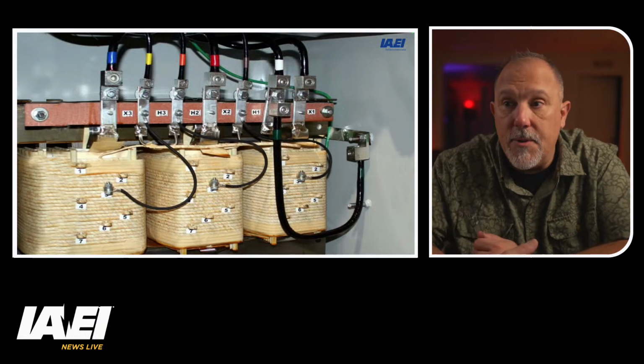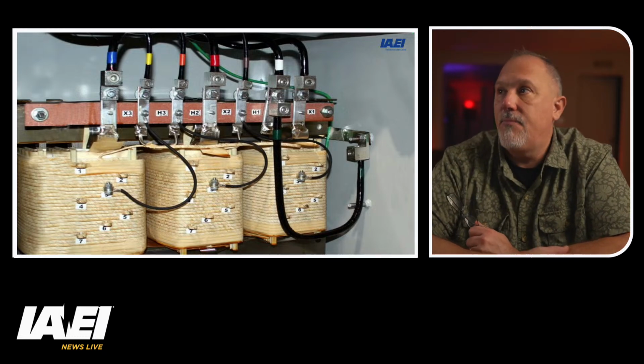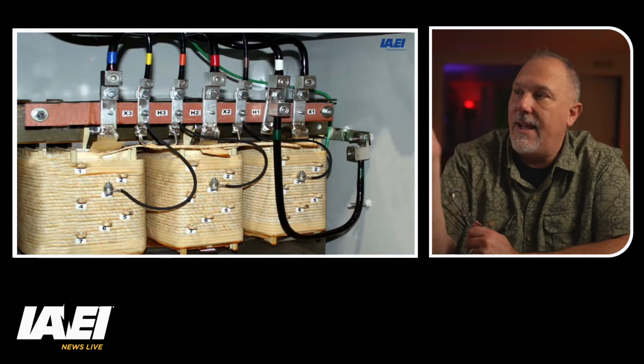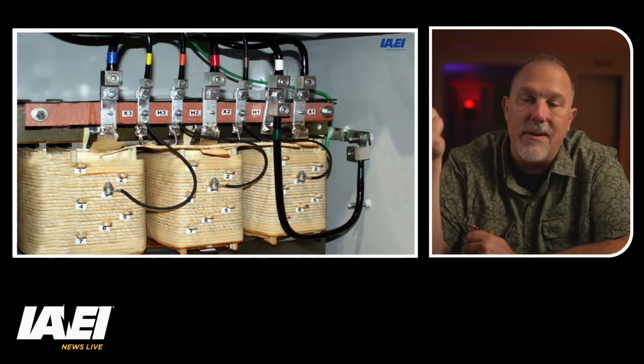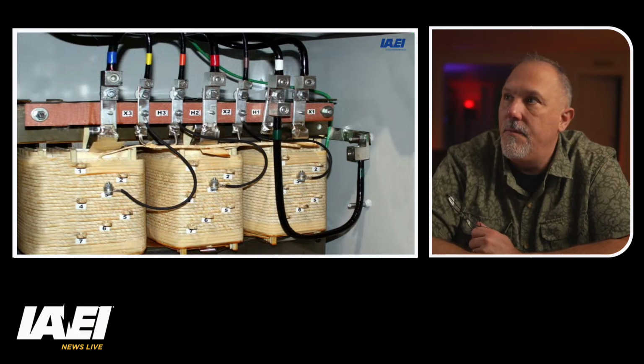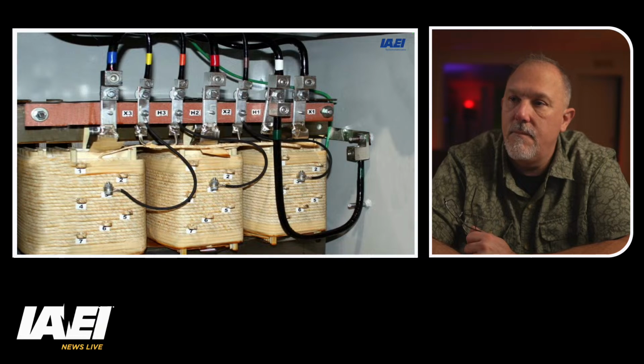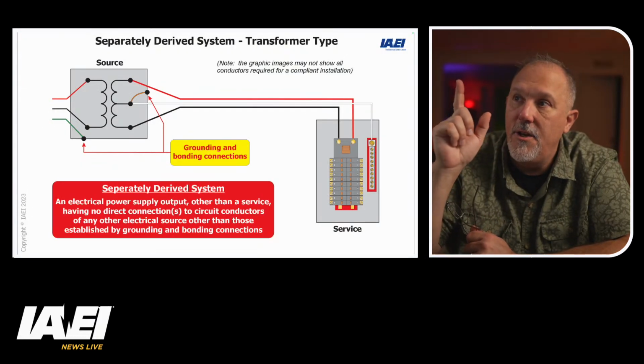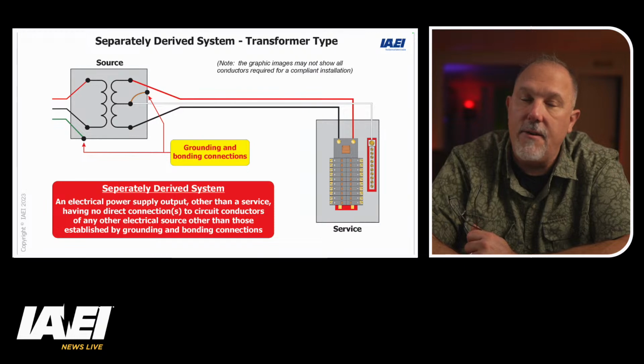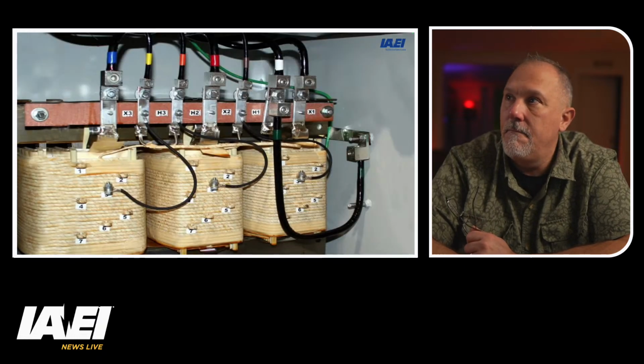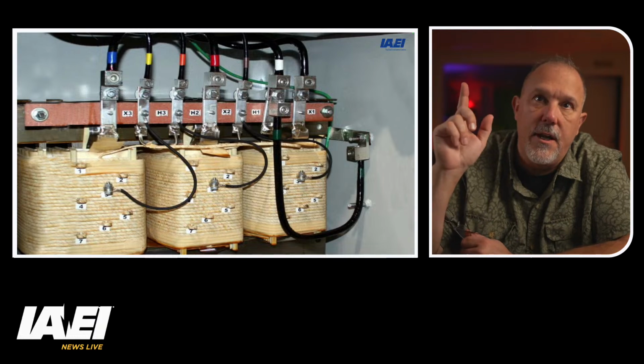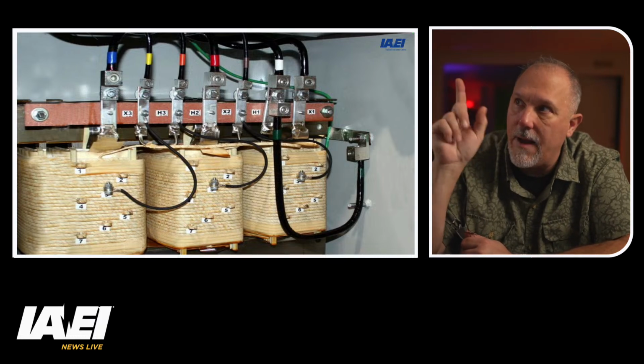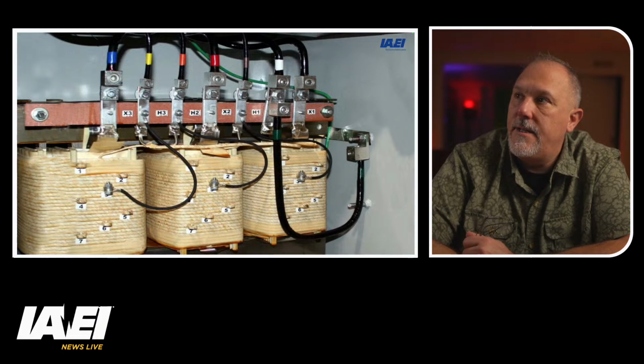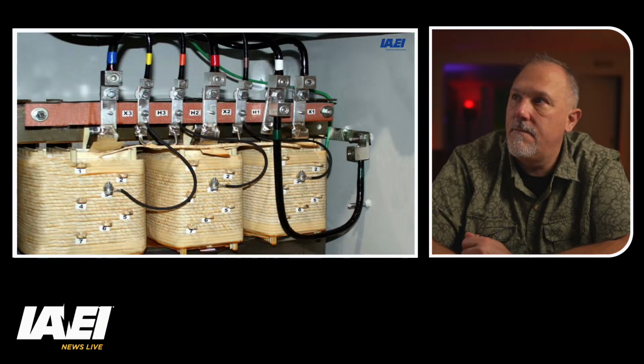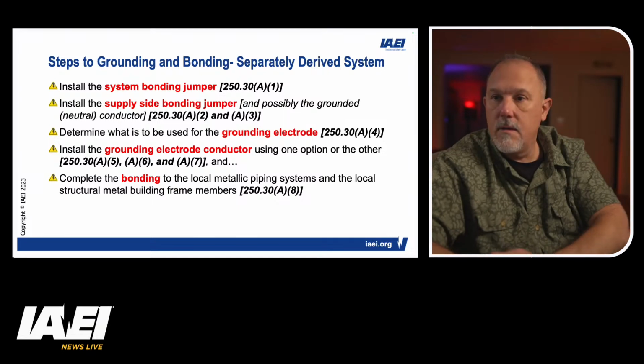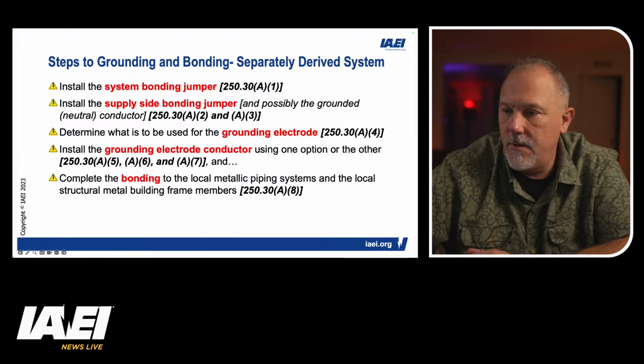There's your typical transformer secondaries and primaries, but you'll notice that big conductor there is bonded to the frame. That's basically what's going on with that grounding and bonding connection there on the secondary. See that conductor has a white label to it, has a white wrap around it. That's your X0.